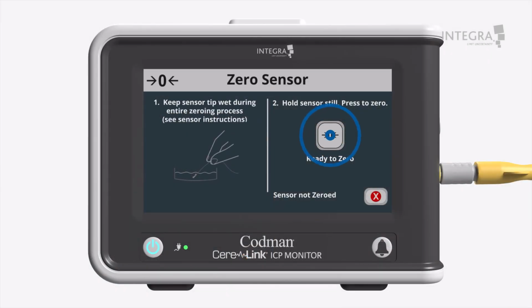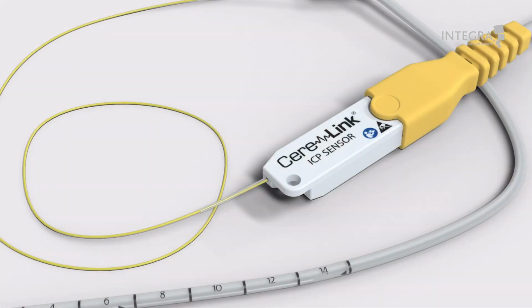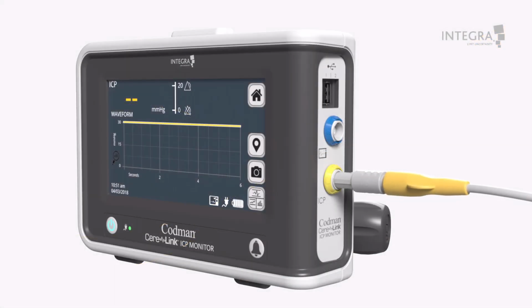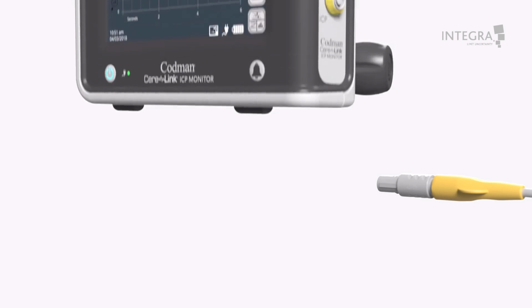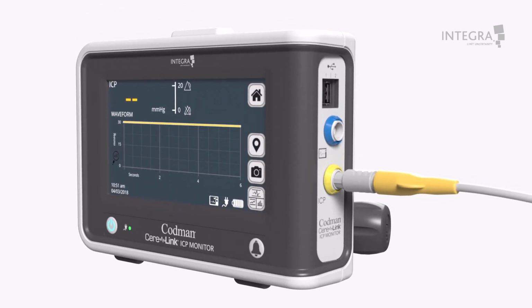Press the Ready to Zero tab. You will note a 0 in progress on the screen. When sensor zeroing has been successful, the date and time will be displayed on the screen. During this zeroing process, the ICP monitor automatically stores the 0 reference value in a memory element embedded in the ICP sensor. This feature allows the user to reconnect the ICP sensor to the same or a different ICP monitor without having to readjust the 0 reference value.